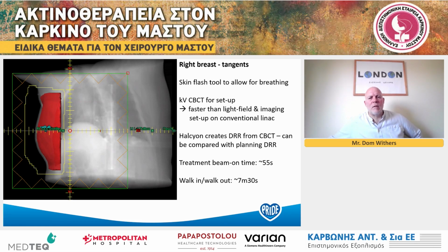Of course, the delivery is fast. This is for 2.67 grays per fraction. But also the rotation of the gantry between those beams is about 7 or 8 seconds. So it's a very, very fast treatment. A typical treatment for IMRT tangents for breast on Halcyon is a walk-in and walk-out time of 7.5 minutes. So setup is very easy and delivery is very fast.